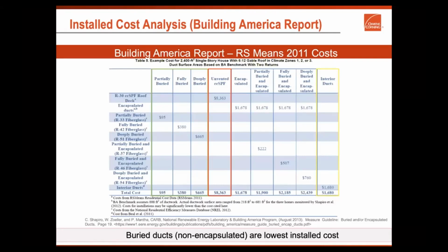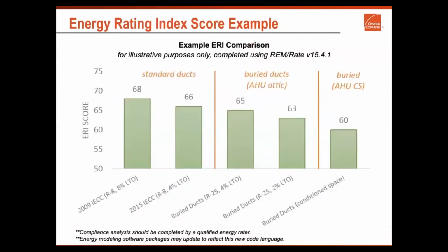Now, one of the things that I always recommend is to test after mechanical, electrical and plumbing are done, before you put up gypsum, because if you have to fix a pipe because someone trampled it or stepped over it, I always recommend doing a duct blaster test then. But most home builders like to do it at the very end, before the homeowner moves in.